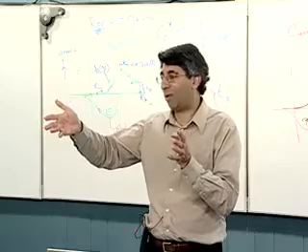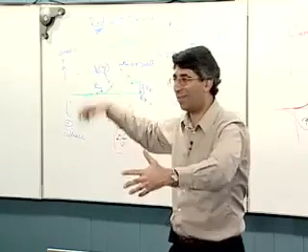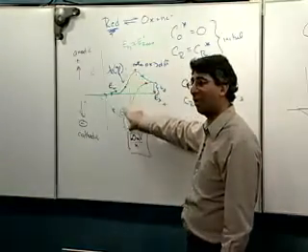Or simply having your working and your reference electrodes too far apart. Or if you were to go and design a working electrode, say that was a flat square centimeter or something, and you covered the back so it was insulating, and you faced that working electrode towards the edge of your beaker, that's your electrochemical cell, and then you put your reference electrode at the other end of the beaker to the back of your electrode, you know, you can induce high uncompensated resistances, and to the extent that you do that, even before it starts to do really ugly things, it will affect your peak-to-peak separation here, which is an important diagnostic, but it's resistance that you're measuring.